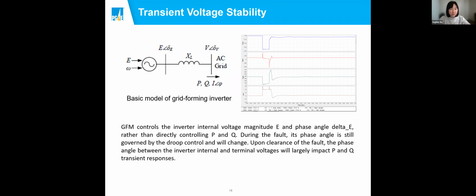current of the inverter. I want to place it here because I think it plays a big role in the performance. So basically in the control, if you allow the inverter to have overload capacity, then you can see a big jump on the Imax during the fault or during the stressed system condition.